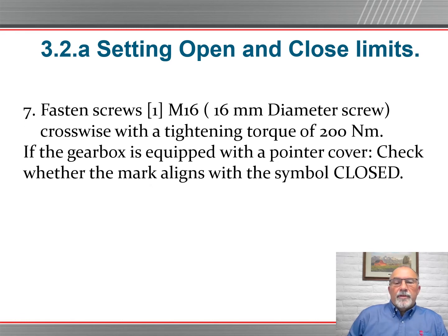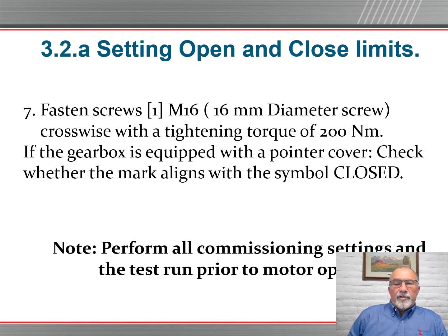Fasten the screws clockwise or crosswise with a tightening torque of 200 Newton meters. If the gearbox is equipped with a pointer cover, check the alignment of the closed symbol. That's something we covered in the previous slide, that big arrow indicator. You want to make sure it's now pointed to the closed symbol. Perform all commissioning settings and a test run prior to motor operation. This is a critical gear setting that should be done in conjunction with your electric operator limit switches being set.